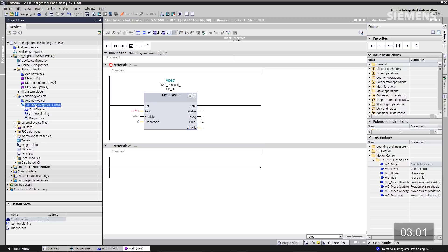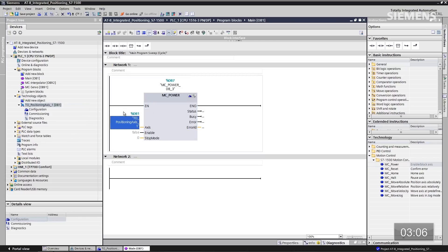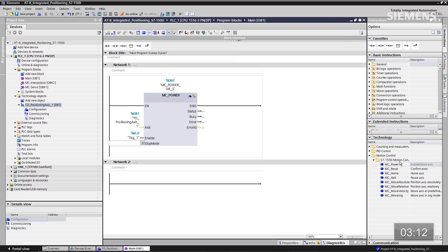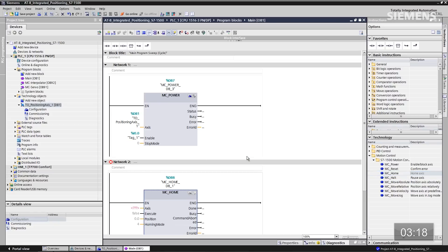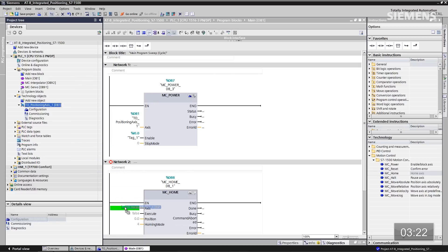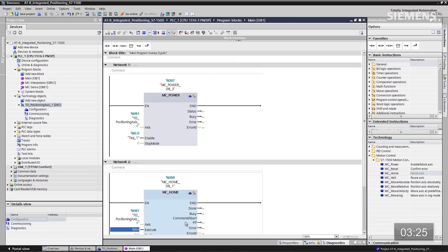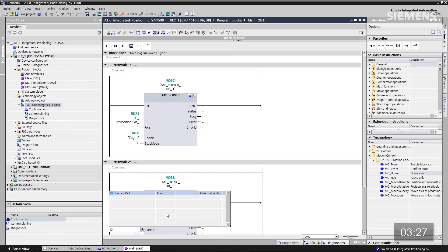Now let's tie this to the technology object we've created for positioning — drag and drop that over to the axis input. I want to enable this using input 0.0, click enter. Now I'd like to add the MC_Home block — drag and drop it into the project, accept the default data block, and tie it to the TO as well by dragging it to the axis input. I want to execute this one using input 0.1.